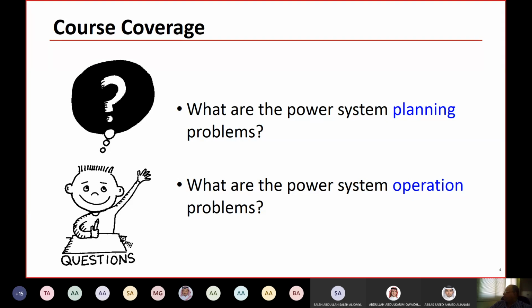Hadi Ali: maybe the type of controller you need to control the generation of electricity or to control the frequency you are generating. You are absolutely right, so control problems - you have to control your frequency. Frequency should be maintained at 60 hertz, and you have to have control on synchronous machines or turbines. If you have thermal or gas plants, you have to control the turbine speed to keep the frequency at 60 hertz. This is called the automatic generation control problem, and it is an operational problem.